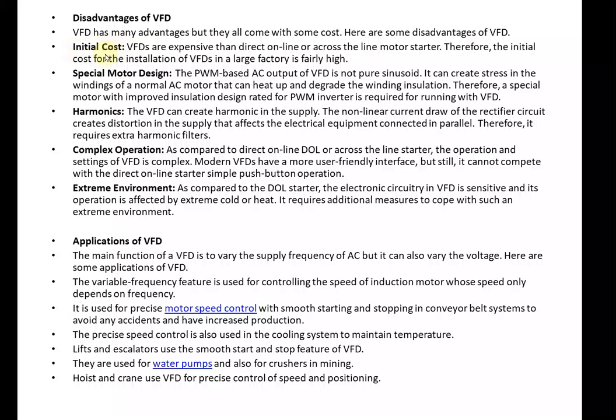There are also disadvantages of the variable frequency drive. First, the initial cost is very high — higher than conventional methods because it is an advanced device. In case of PWM-based AC output, the output is not pure sinusoidal and can create stress in the windings of the AC motor, which can heat up and degrade the winding insulation. Therefore, a special motor with improved insulation design rated for a PWM inverter is required when running with a VFD, which also increases cost. There are also harmonics because we are changing frequencies and voltages.